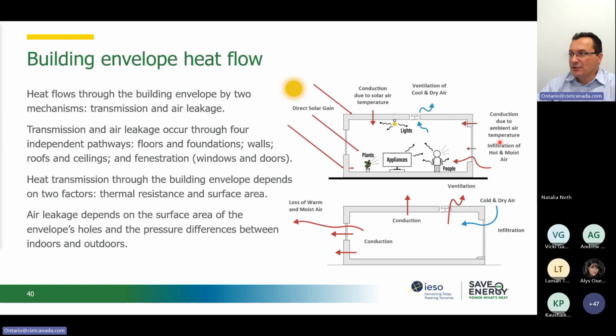We have infiltration that will be present in our buildings. This is basically because we have different pressure inside the building versus outside, either due to wind or due to unbalanced HVAC systems. So this is heat exchange with the exterior, and then inside the space we have heat that we need to address. So we have sources of heat, internal loads, which could be people, appliances, or equipment in the building. We also know that our buildings need ventilation, fresh air. So we have exhaust air to allow for that fresh air to come in. So we do have to deal with a fairly complex problem here. To improve the efficiency, we have to basically use all those modes of heat transfer that I mentioned in a proper way.